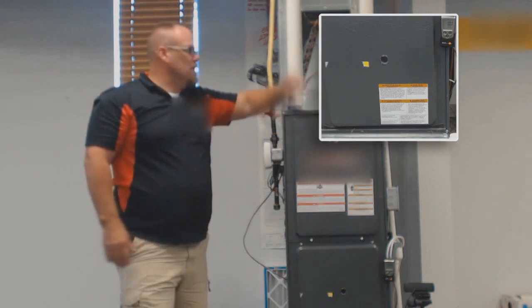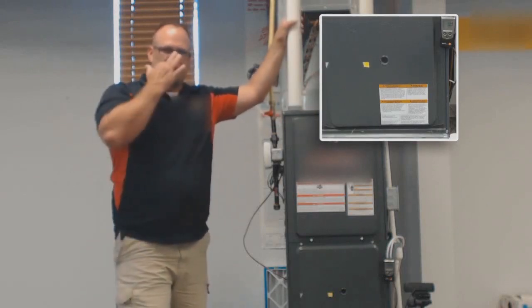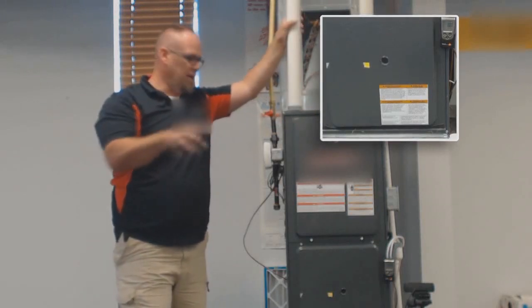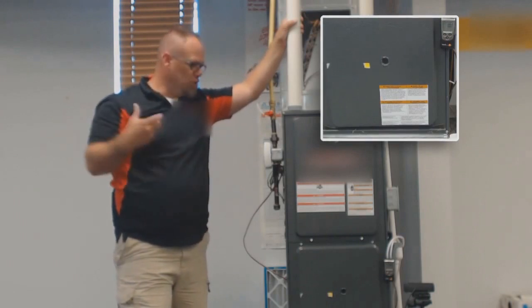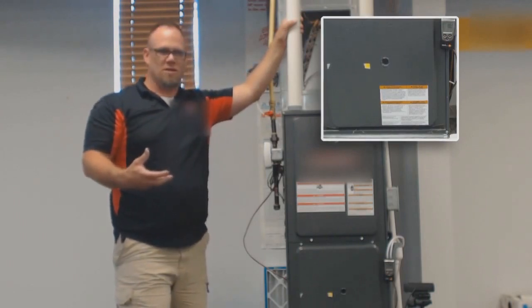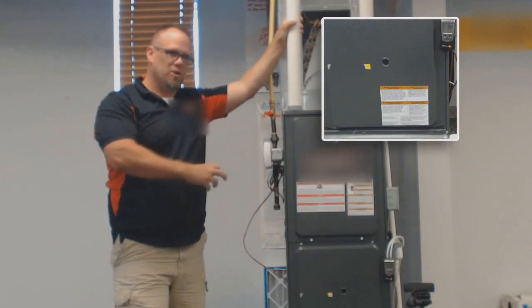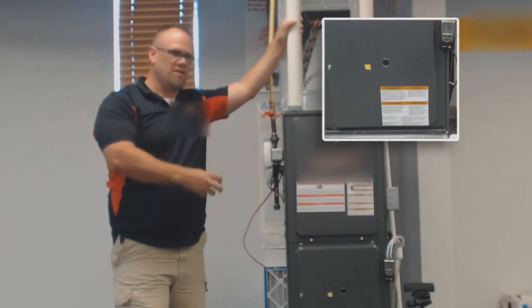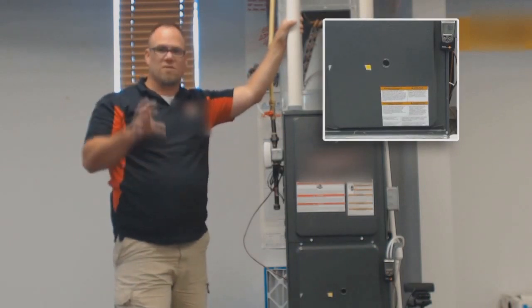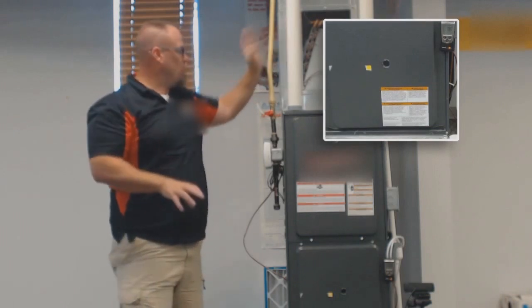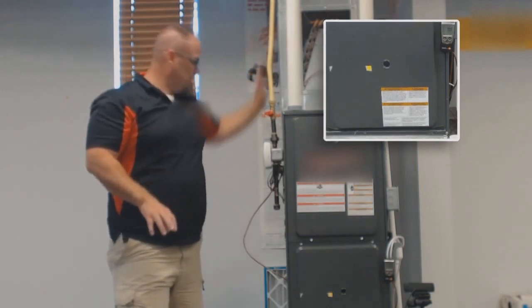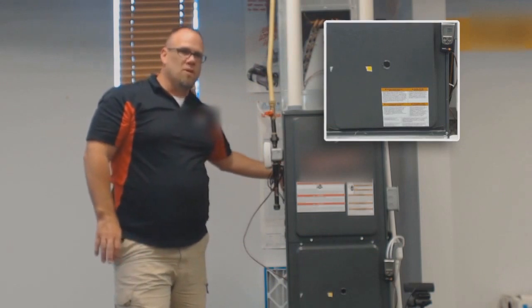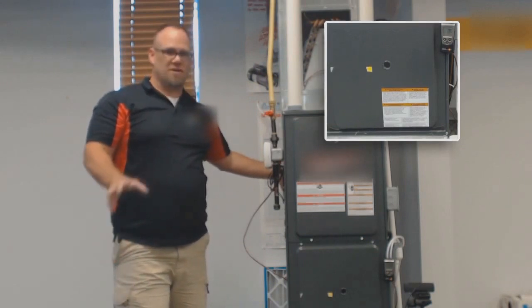My name is Corey Paper. We're going to go over the adjustment of a blower in a gas furnace. And in doing that, what I focused on is how simply changing the blower speed to set it up properly for the manufacturer's guidelines, to make sure that you've got the proper CFMs going across this coil for air conditioning and across this heat exchanger for heating, makes all the difference in the world.